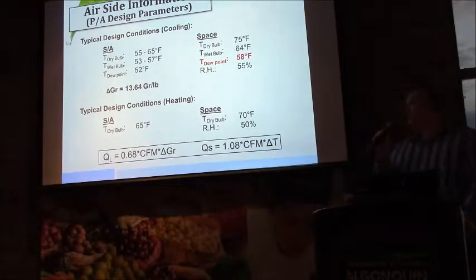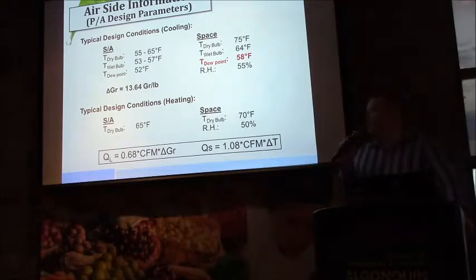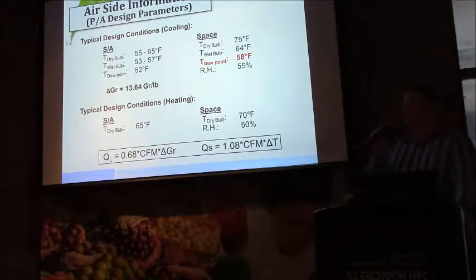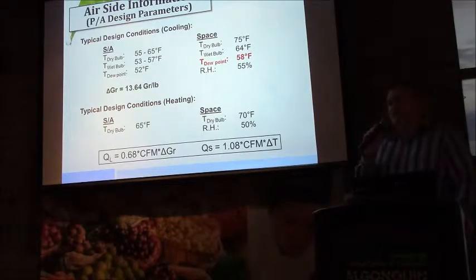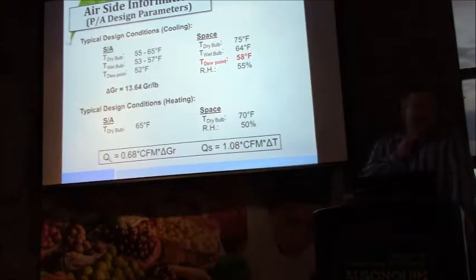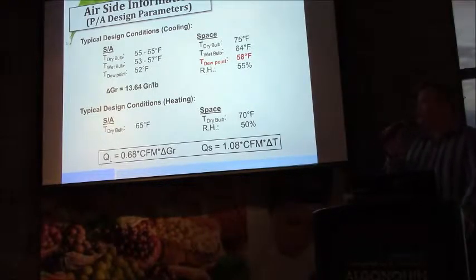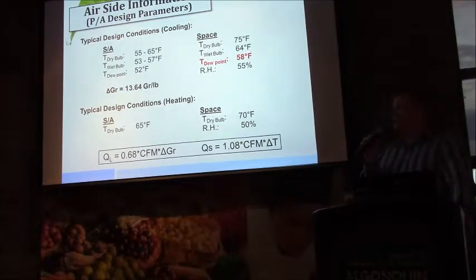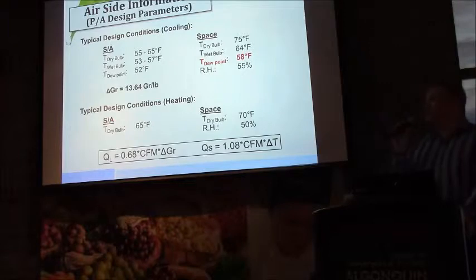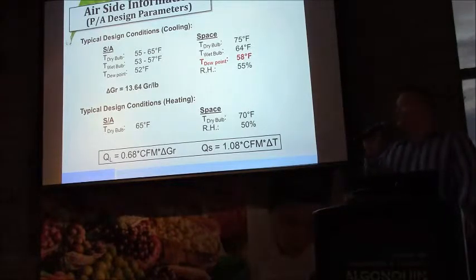Beams aren't a silver bullet, and they're not for every space, and they do have limitations, one of which is overhead air distribution in heating mode. When we discharge from the beam, it's critical to check the supply air temperature at the discharge of the beam to the space to ensure that we get appropriate pattern or good flow and mixing in the space. Generally that would restrict us to a supply air temperature no greater than about 15 degrees Fahrenheit above the set point of the room. So if the room was designed for winter heating at 70 degrees, generally we would restrict the discharge air to 85, to ensure that the room air was mixed thoroughly and heated the space without creating a thermocline.